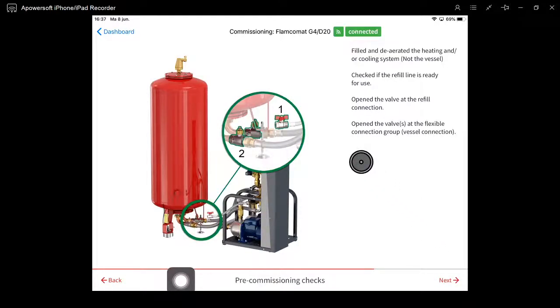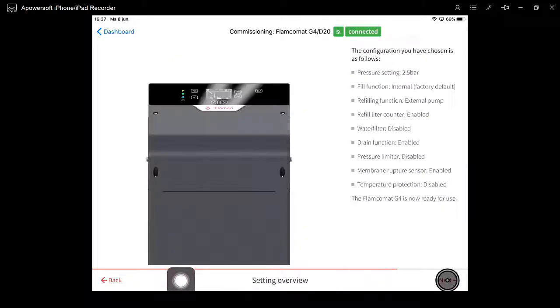Then we have to deaerate the system, check if the refill line is ready for use, open the valve at the refill connection, and open the valve at the flexible connection group. Then I can press next.